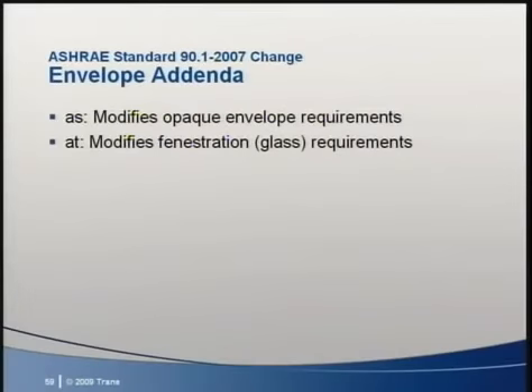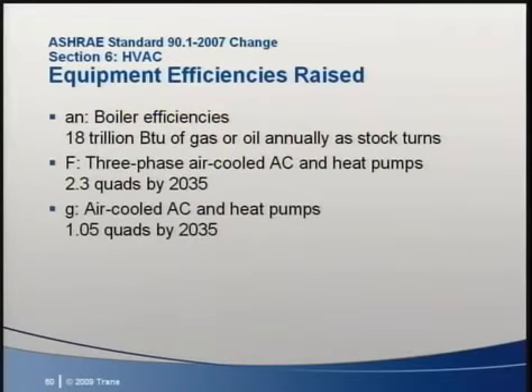Significant changes were made to the envelope section of 90.1. Both the opaque elements, walls, roofs, floors, etc., and fenestration or glass requirements changed and generally became more stringent. This means that heat conduction loads and solar loads should be reduced. In the mechanical section, equipment efficiency increases occurred for boilers, three-phase air-cooled air conditioners and heat pumps, and air-cooled air conditioners and heat pumps. The SSPC attempted to estimate the savings based on implementation of each addendum. The estimates shown on the slide are taken from the forewords of each addendum.